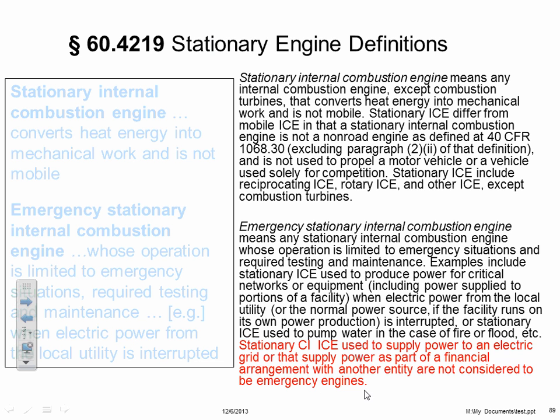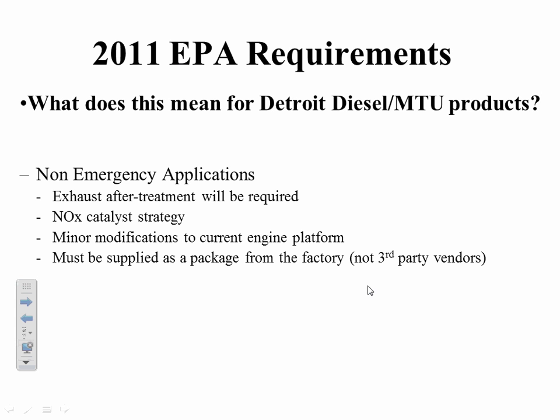So why are they making that point? Because there's going to be different emissions requirements. You can still do the program with the utility, but you've got to bring your existing generator set or new generator set, if that's what you're designing for, up to a new emission standard. Exhaust after treatment will be required. A NOx catalyst strategy on new engines. Minor modifications to the current engine platform are needed. And it must be supplied as a package from the factory. That's really not true anymore, and I should take that line out.